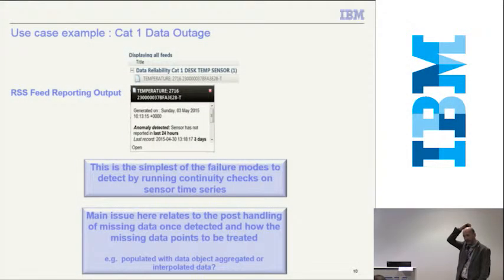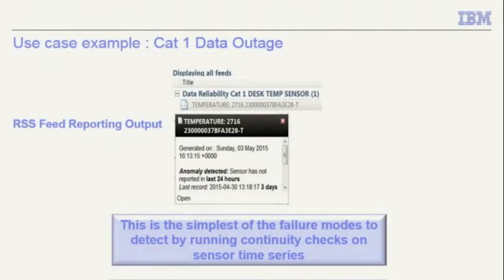So this is an example from one of the systems we have, and what we've done is set it up as an RSS feed, because particularly when we were starting off, we were getting all these false alerts, so we didn't want to crowd up our texts or our email system. In Outlook or in Lotus Notes that we use, there is an RSS feed reader. So basically all you do is subscribe to sensors that you're interested in. I'm interested in certain sensors, Niall is interested in other sensors. Charity's not interested in any sensors. So we just subscribe to these, and we can look on a daily basis. You can set how often it refreshes and all that sort of stuff, so you can control how many messages you get.